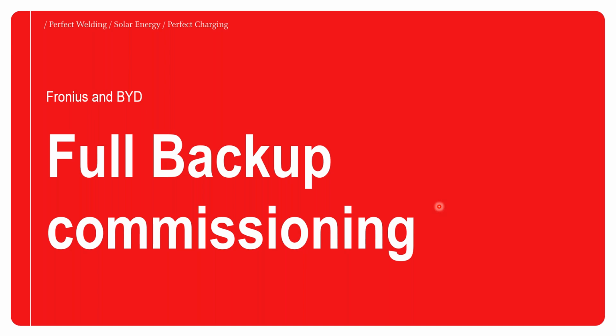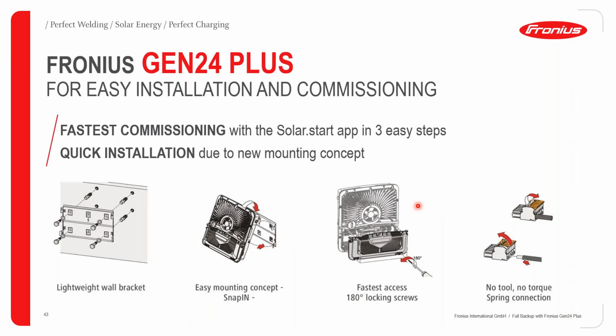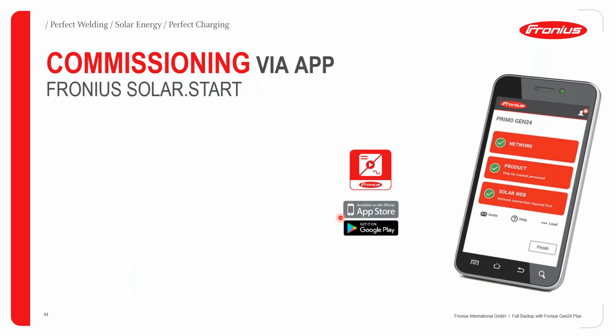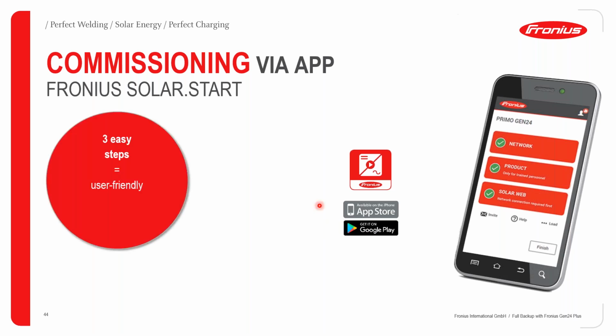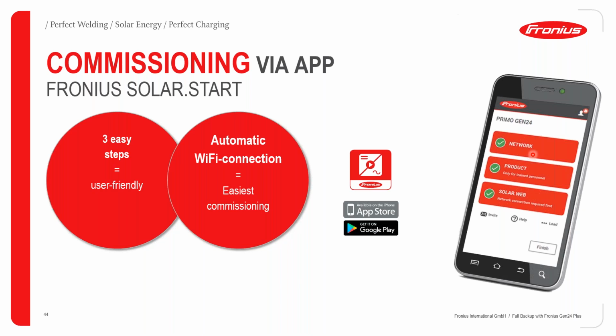Now let's talk about the commissioning. Just to give you a roundup, it takes a good installation to have a successful commissioning. So ensure that your installations are correctly done. And once that is done, you only need to go through 3 easy steps for the commissioning. This is made possible via our new app that was launched a couple of months ago, which is the Fronius Solar Start app. These 3 easy steps include connecting your product to the network, inputting the product specification, and then connecting to SolarWeb.